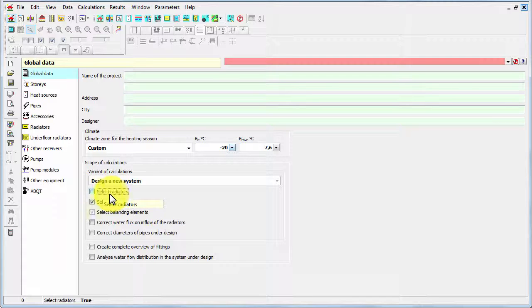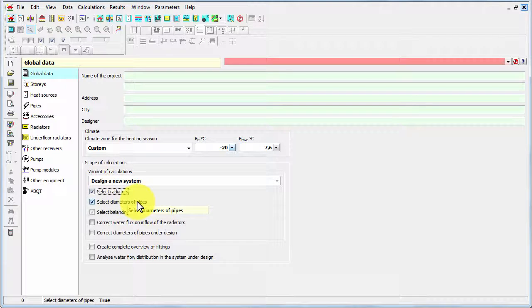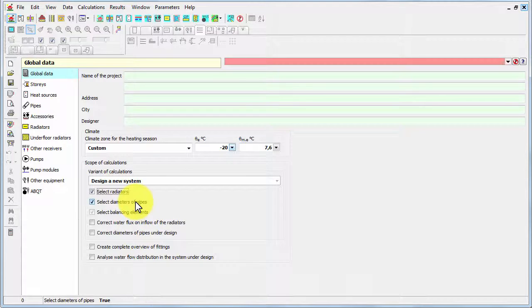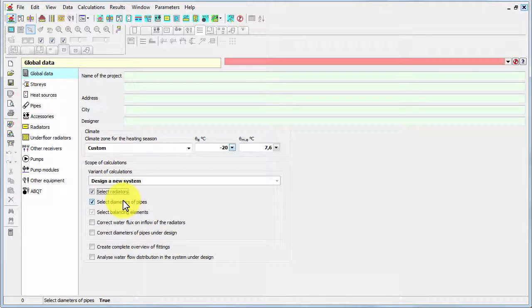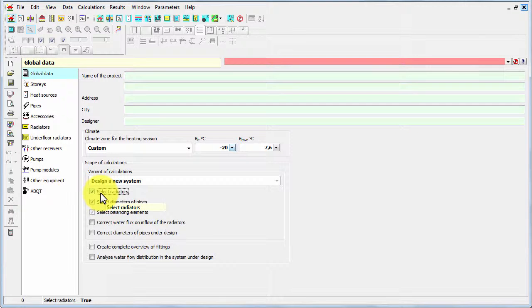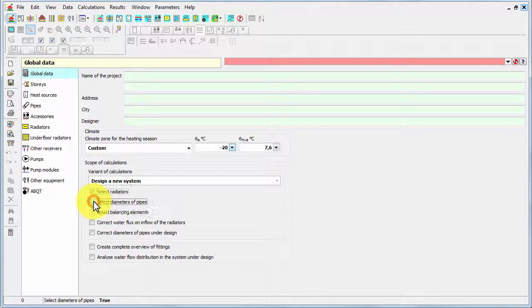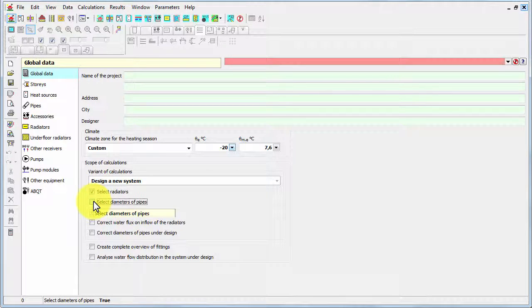But if you balance an existing system without changing radiators, then you should switch it off and then you will have to enter all the sizes of radiators manually. In the same way the next option works - selecting of diameters. In case of designing a new system we will have it on. But if we balance or rebuild the existing system without changing the pipes we can switch it off, and then we will have to enter all the diameters.